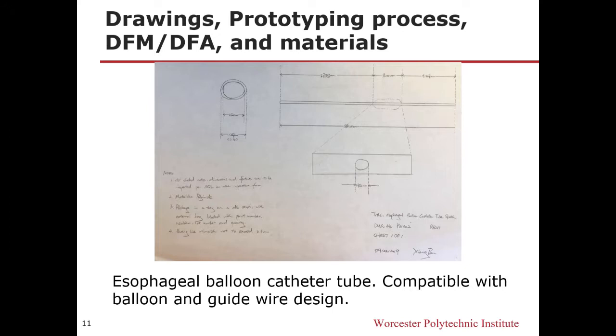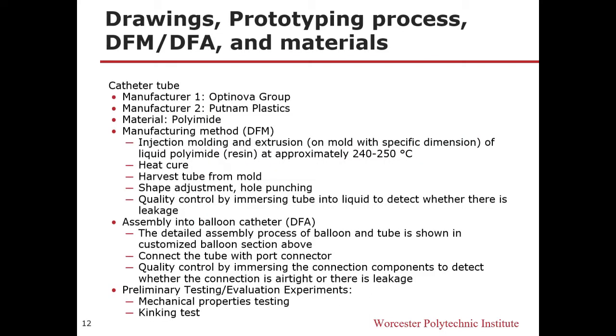Now I'm going to talk about the catheter tube, which is 5 French in outer diameter and approximately 86 cm in total length. The location of the balloon is at approximately a third of the catheter length away from the distal end. We have a small hole, which is 0.75 millimeters in diameter, to supply gas into the balloon. The catheter tube should be compatible with the balloon and the guide.